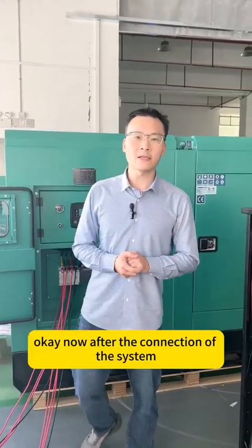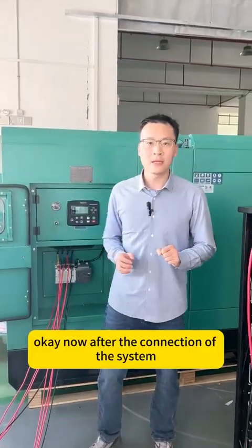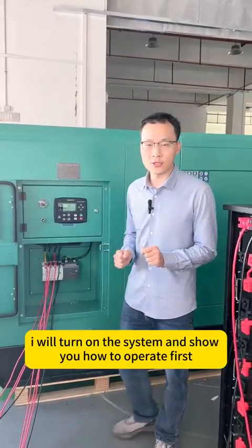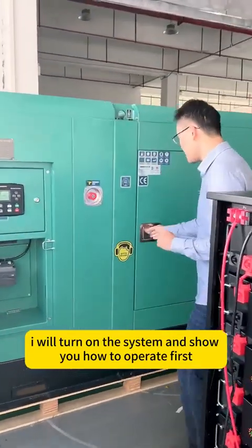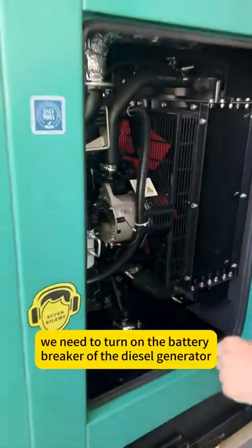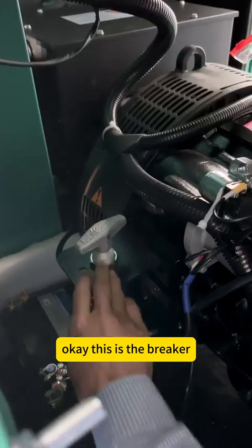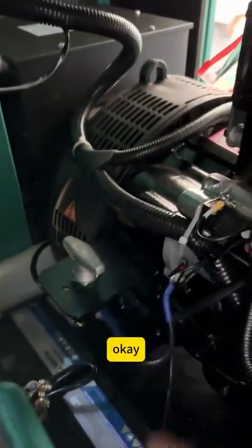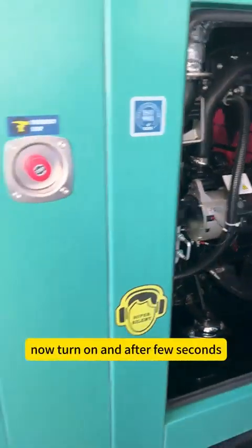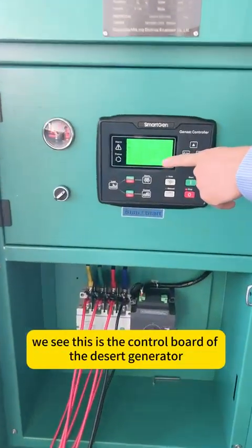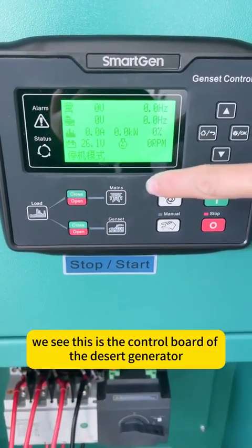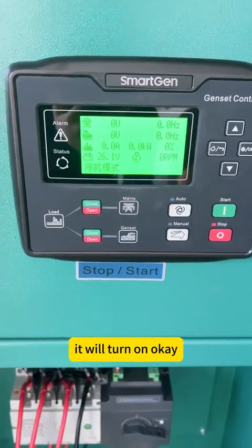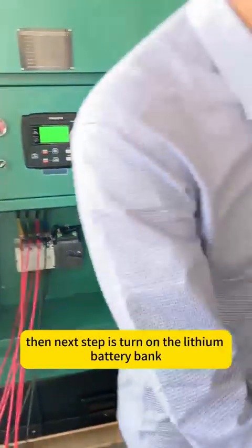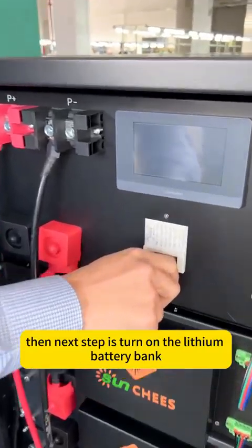Okay, now after the connection of the system, I will turn on the system and show you how to operate. First, we need to turn on the battery breaker of the diesel generator. Okay, this is the breaker. Now turn on, and after a few seconds, we see this is the control board of the diesel generator. It will turn on. Then the next step is to turn on the lithium battery bank.